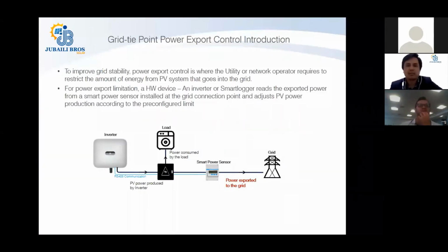For the grid tie point power export control options, you need multiple devices. The basic one is the inverter itself. In regard to the inverter, you will also need a smart logger or a dongle of Huawei. These are the two optional items, but depending on the project scenarios, you might have different combinations of inverters. In the next slides, we'll go through in detail the different scenarios and types of projects you might have, and what type of control options you have with such different types of inverters.